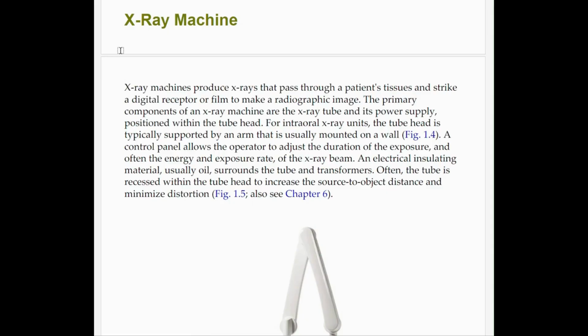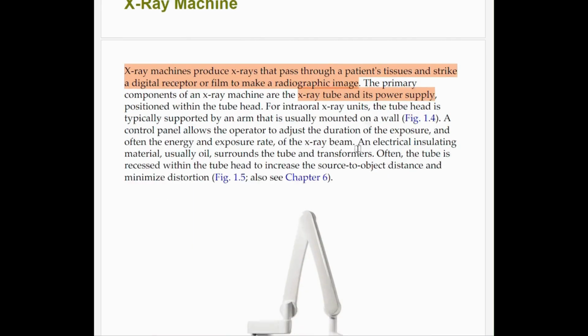First, we will draw and describe the X-ray machine. So, what is the use of the X-ray machine? It produces the X-rays that pass through a patient's tissue and strike a digital receptor or the film to make a radiographic image. The primary components of an X-ray machine are the X-ray tube and its power supply, which are positioned within the tube head. For an intraoral X-ray unit, the tube head is typically supported by an arm that is usually mounted on a wall. That is the normal IOPA that we take in our college.